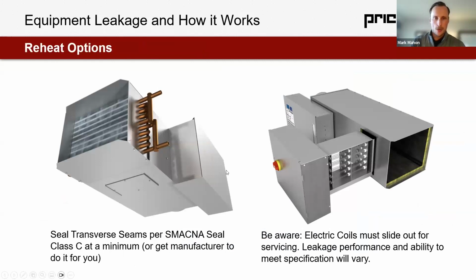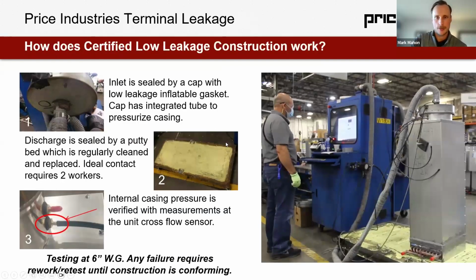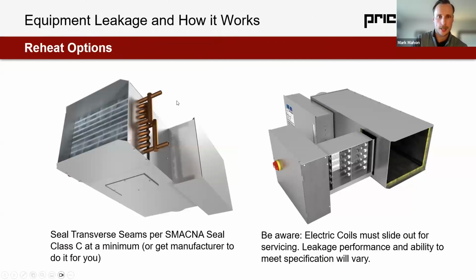So, equipment leakage and how it works. Another thing I want to note here is our reheat options. Sorry, I had one slide there. When we look at reheat options, different reheat options also operate quite differently. A transverse seam for a hot water reheat coil generally is going to get your leakage performance for the terminal within spec and is very easy and manageable to do in the field.